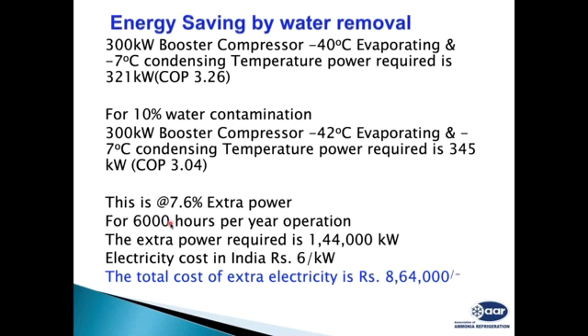This is a typical cost calculation example, a feedback example of what happens when we have water in the system. For a 300 kilowatt booster compressor at minus 40 degree evaporating and minus 7 degree condensing, as it is a booster compressor, and I told you the water will occur only at the low pressure side. So at minus 7 degree condensing temperature, power required is 321 kilowatts at a COP of 3.26. This data has been collected from some compressor manufacturers' software.